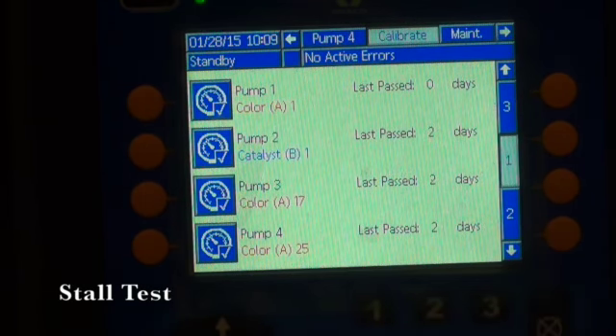On the original calibration, once you just loaded your pump, you might have to run it 2 or 3 times. There could be air bubbles in there that get eliminated at this time, and if there is any air in the system, most likely the calibration will fail.